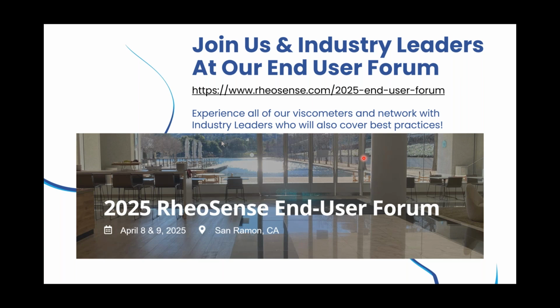So I'd like to continue on. I have a couple more questions. Thank you for the presentation. Is it possible to clean the old MVROC with acetone as well? Yes, very possible. Next question: when there are bubbles in the samples, will it damage the VROC chip? The answer is no, it will not damage the chip.